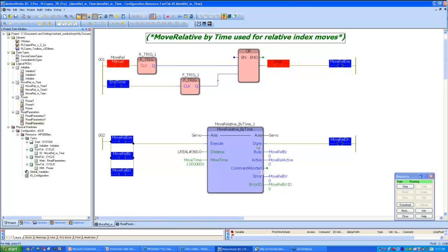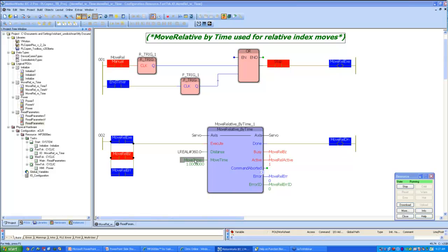While the axis is in motion, the Busy and Active bits are on. Once the axis completes its motion, the Done bit comes on. In this case it comes on for only one scan, so it will be difficult to visually verify.